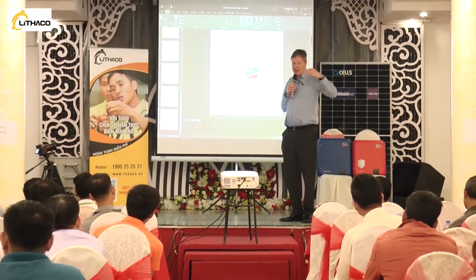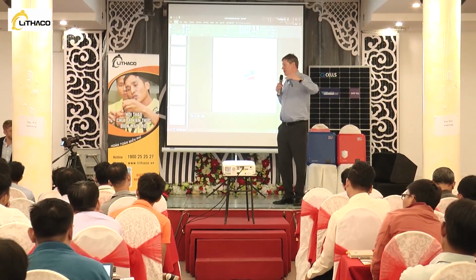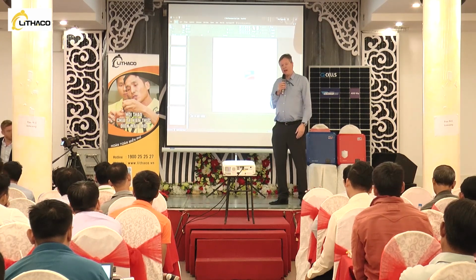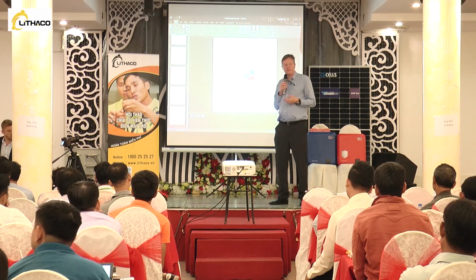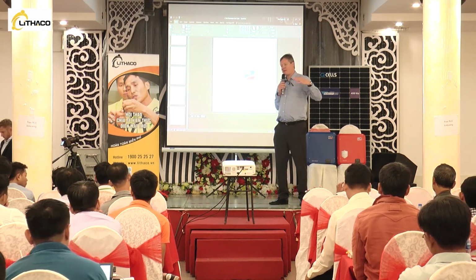But what I would say is if you've got a grid with occasional high voltage, the inverter might switch off, but when the voltage returns to normal, it will switch on again. And as I say, the inverters are designed in Germany, they're manufactured in Germany, it's a strong product, it's a Mercedes. It's not going to be damaged by the high voltage, but it will switch off to observe the protection settings of the grid.